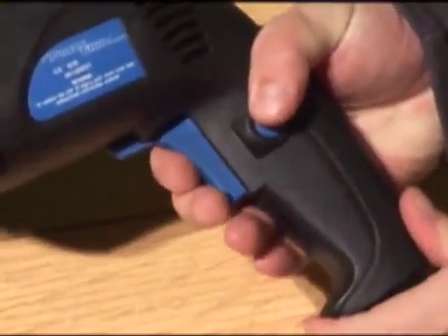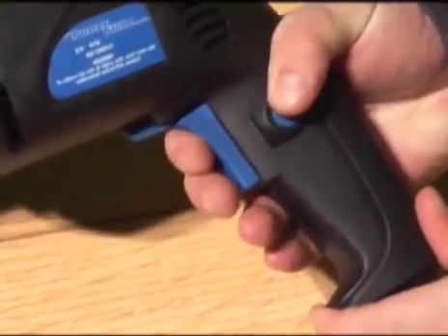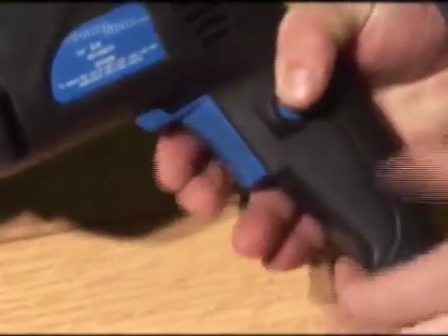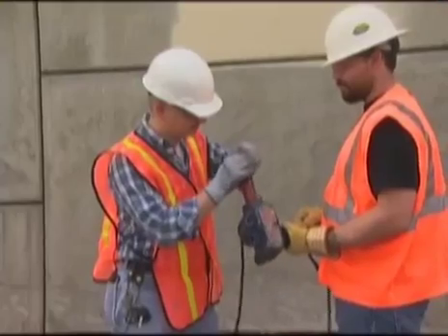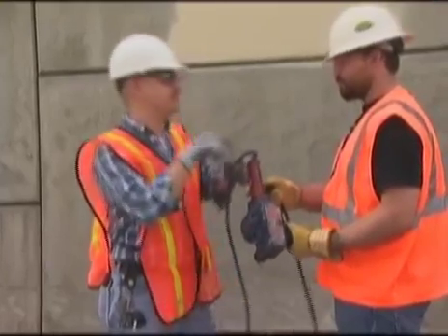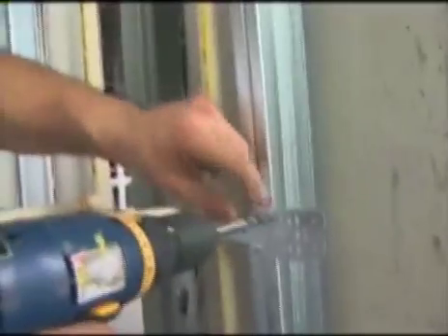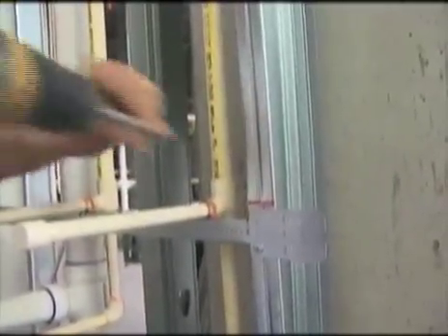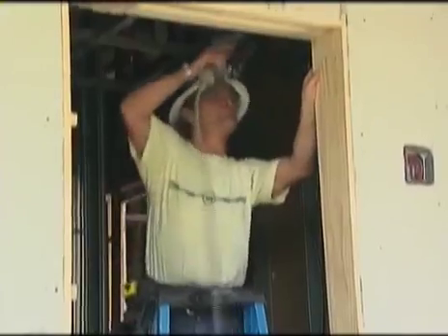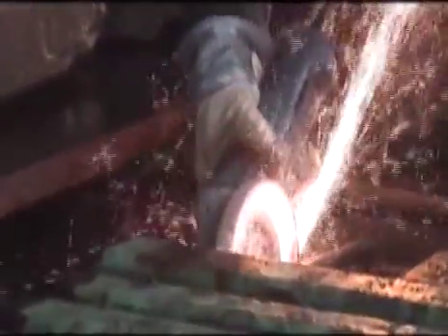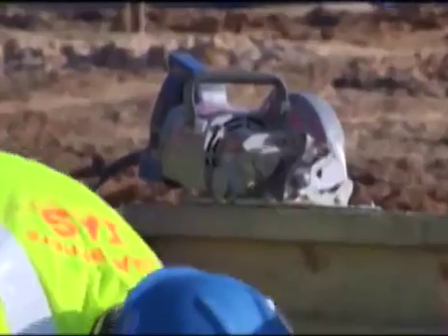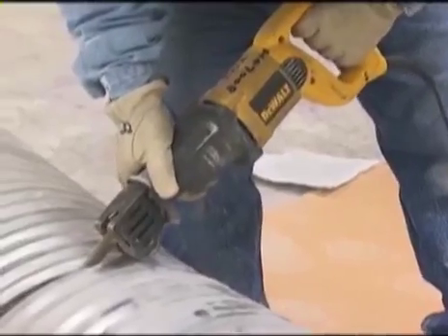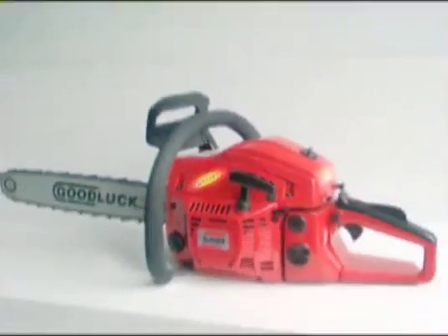Handheld portable power tools are to be equipped with a constant pressure switch or control that shuts off the power, thereby stopping the tool when pressure is released. Many older portable tools do not have this feature and should not be used. Tools that must be equipped with this safety switch are drills, tappers, fastener drives, horizontal, vertical, and angle grinders with wheels more than 2 inches in diameter, disc sanders, reciprocating saws, saber saws, and similar tools.